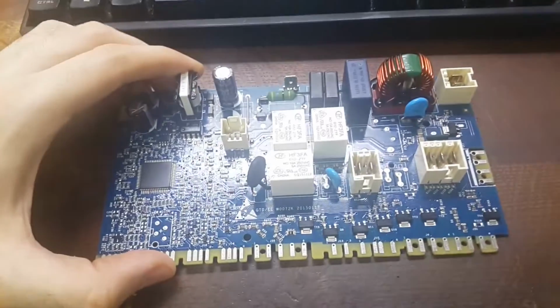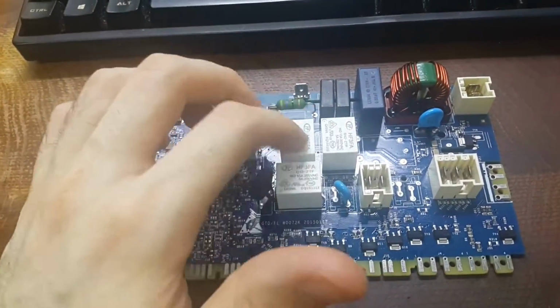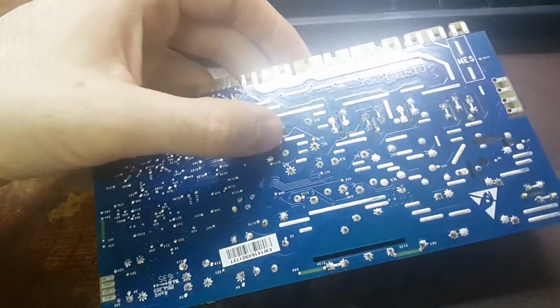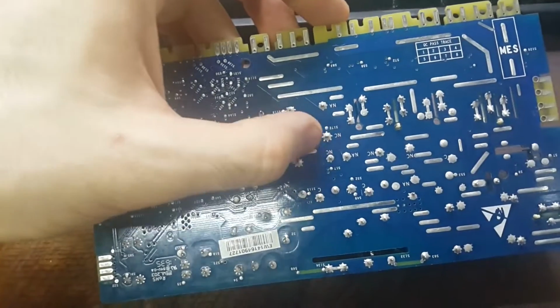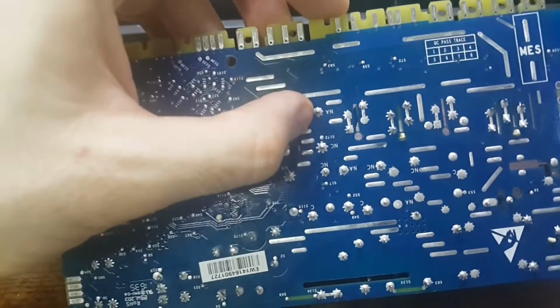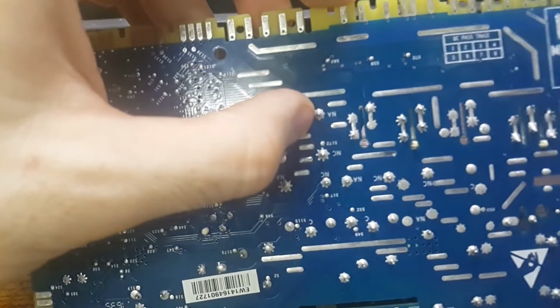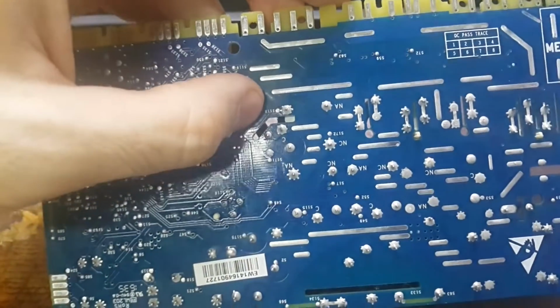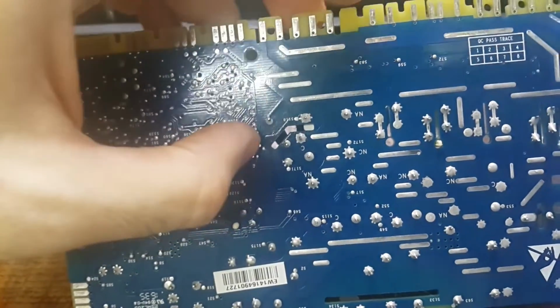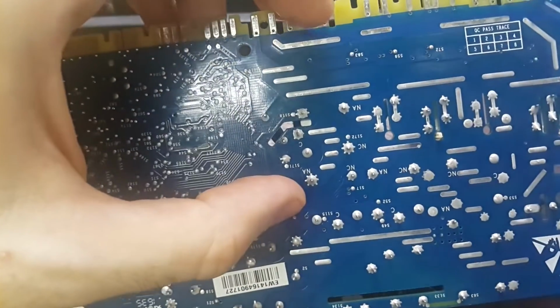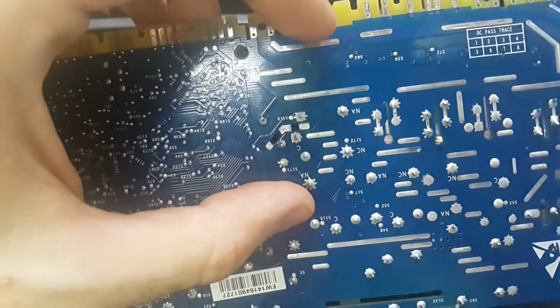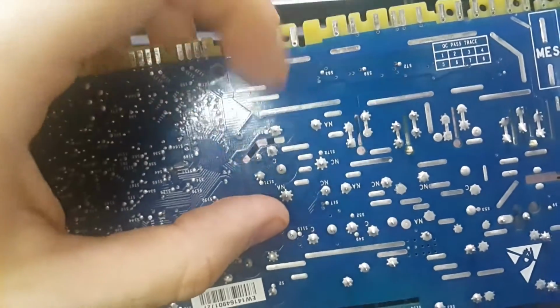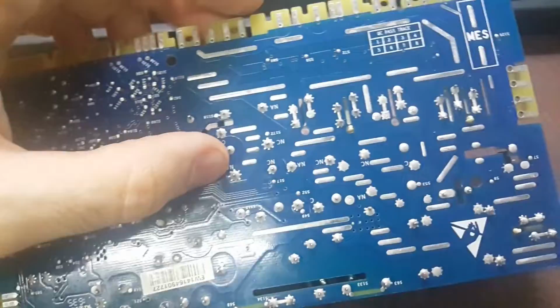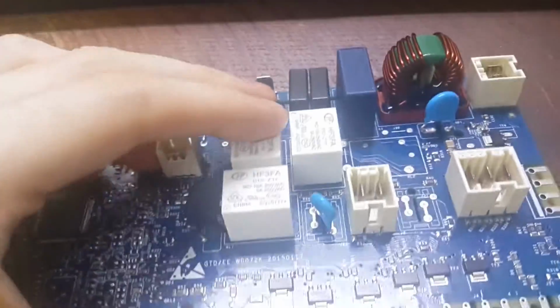The heating relay has got to be one of these, so I tested all the relays. Looks like 3 of the contacts are marked common, normally closed, and then normally open I guess, but it says NA, so maybe it's normally open. And there's then 2 more for the coil. So I just put voltage on there and cranked it up until I heard a click, and checked the voltage and resistance - all of these relays are just happy, so it's not the relay itself.